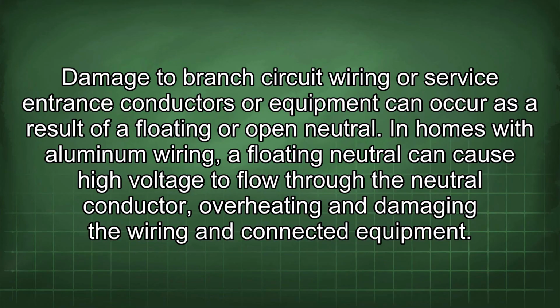Damage to branch circuit wiring or service entrance conductors or equipment can occur as a result of a floating or open neutral. In homes with aluminum wiring, a floating neutral can cause high voltage to flow through the neutral conductor, overheating and damaging the wiring and connected equipment.